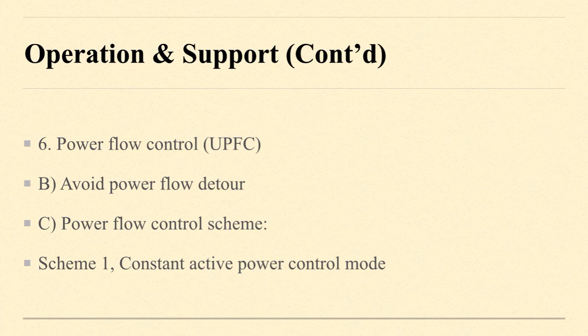Next is power flow control, UPFC. First, transmission capacity analysis. According to the current scale of wind power, the maximum power transmission capacity is limited by the capacity of the converter station at the sending end. In actual operation, it is necessary to allocate the power flow to avoid current limiting overload.